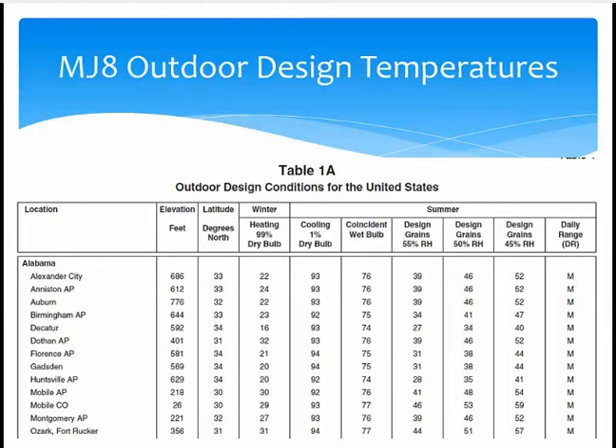Here's an example of table 1A's layout. The leftmost column is location — here, all cities for the state of Alabama. Moving to the right, the table gives us the elevation, latitude, heating 99% dry bulb temperature, cooling 1% dry bulb temperature, the coincident wet bulb, the design grains for 55, 50, and 45 percent relative humidity, as well as the daily temperature range for each city. For example, Birmingham Airport: the 99% dry bulb for heating is 23 degrees Fahrenheit, and the 1% dry bulb for cooling is 92 degrees Fahrenheit. The median daily range for Birmingham Airport is medium, meaning the temperature swing throughout a normal day is not going to vary that much.